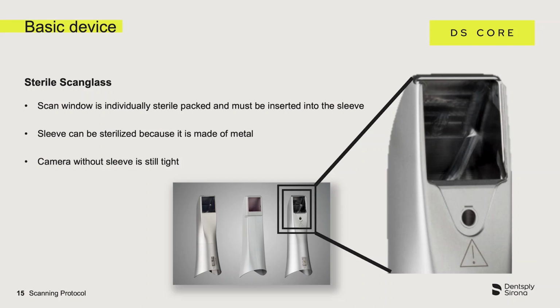The third available scanning sleeve is intended for intra-operative use. Sterile requirements have to be met here. Therefore, this sleeve is delivered in two parts. First, a metal sleeve and individual packed scanning glasses. The metal sleeve can be sterilized and assembled with the individually packed scanning glass. Since the camera is still a closed system, even without the sleeve, intraoperative use is therefore guaranteed.